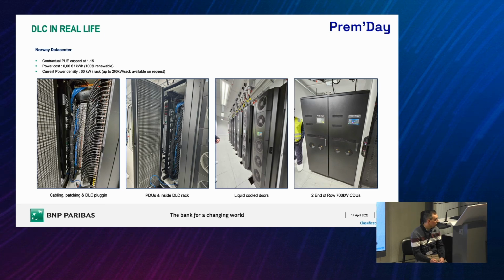Those are some pictures from our liquid cooling system recently installed in Norway. So we have a PUE capped at 1.15. Our power cost is 0.06 euro per kilowatt hour. So it's around 0.18, I think, in France today, depending on the contract you have. We have a power density of 60 kilowatts per rack. As we don't pay for space, we limited the density to the number of ports that we have and the number of available ports also on the manifolds, which are installed on the back of the racks.